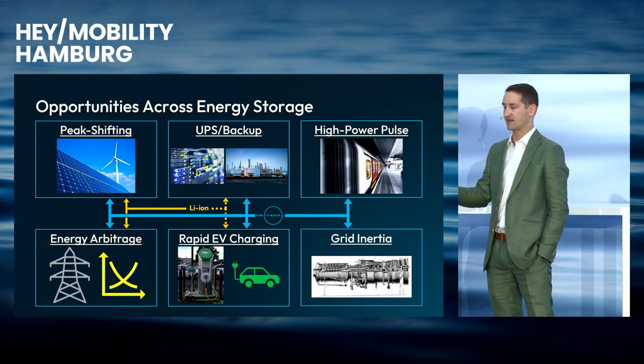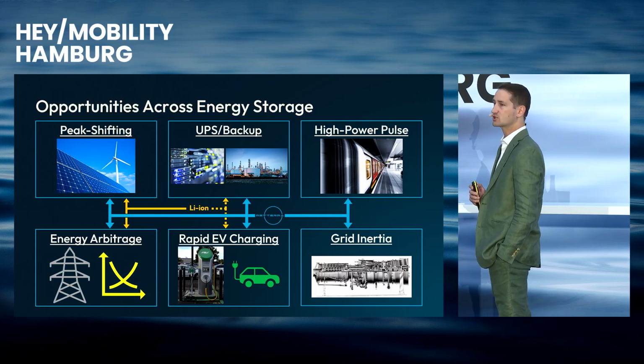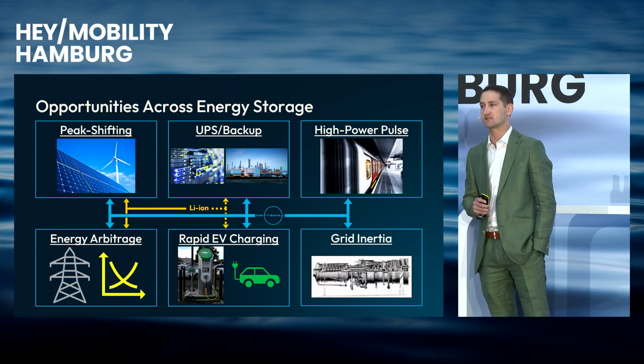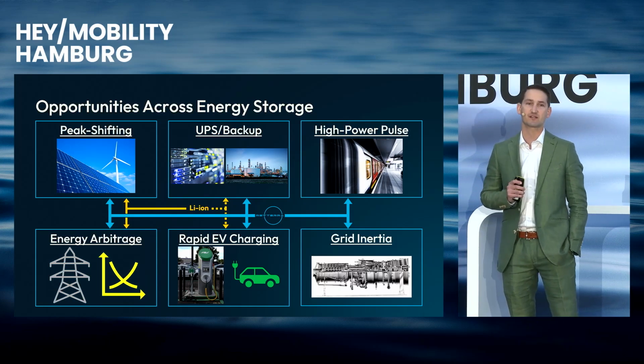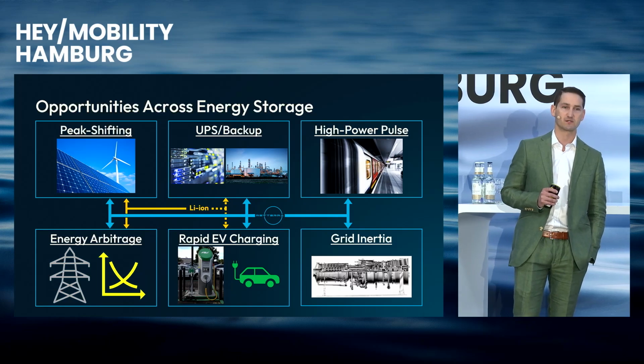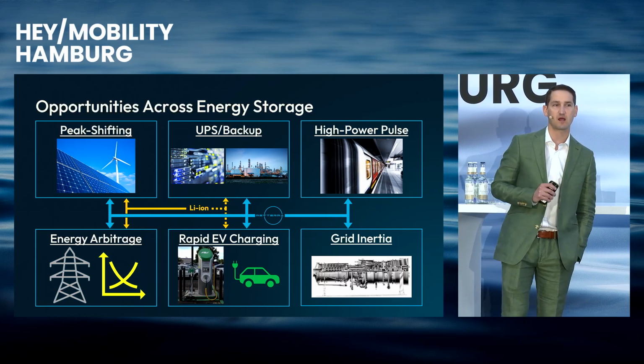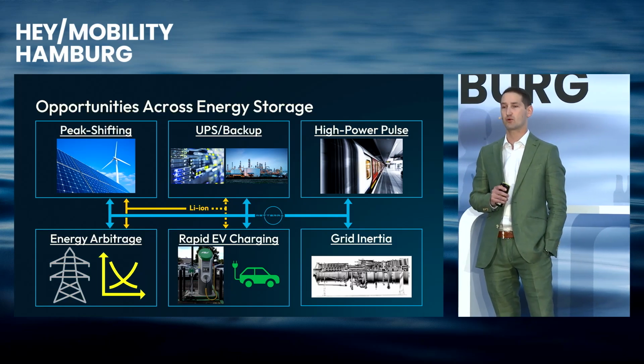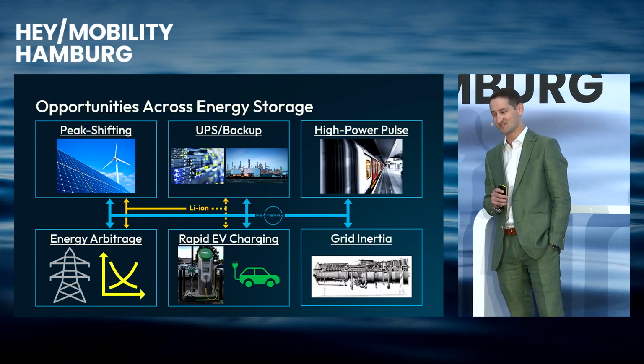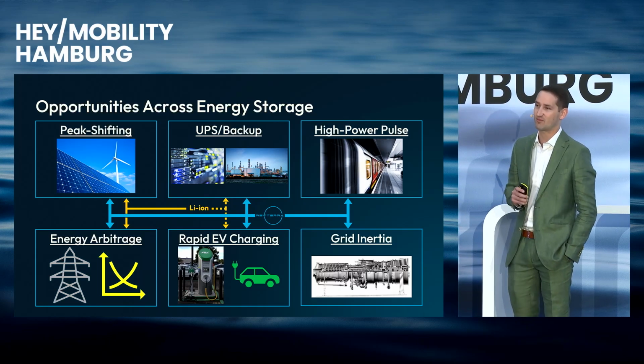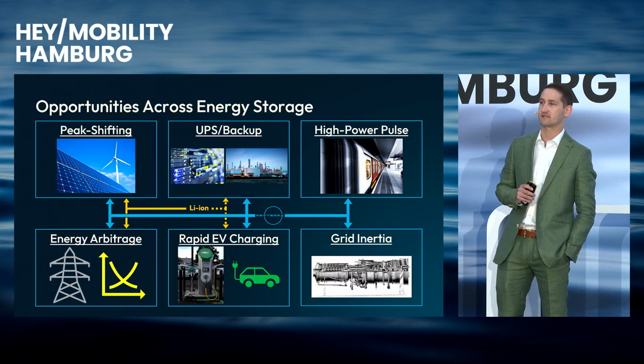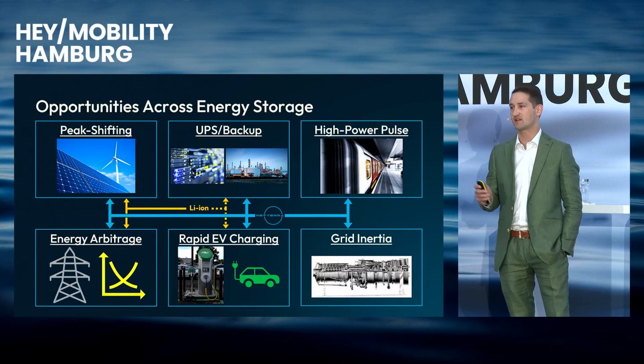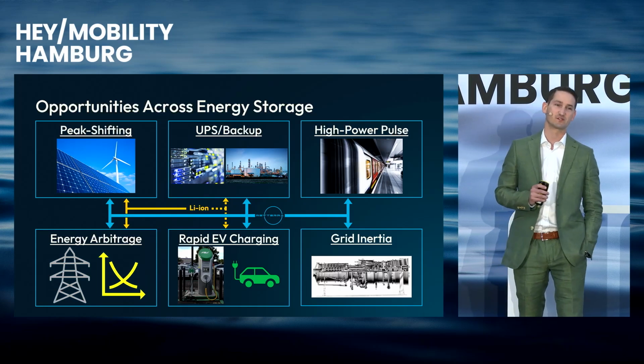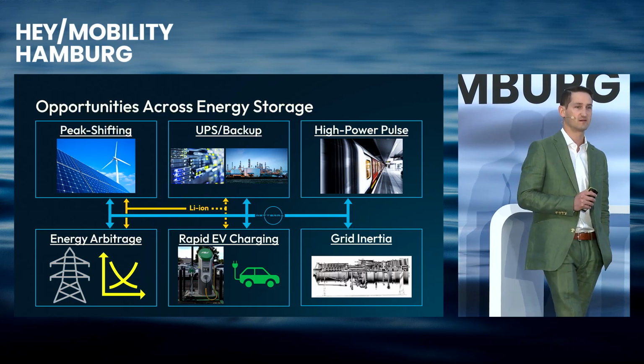We can also provide critical industrial and commercial backup power at sites in a way that is substantially faster than existing UPS solutions. Because our rotating device operates grid frequency synchronous, we can provide backup power physically instantaneously, meaning you don't need to wait the 15 to 20 milliseconds typically associated with backup power devices.